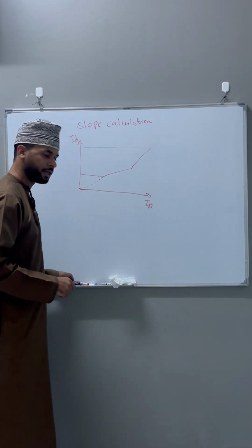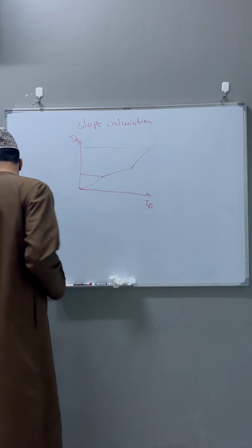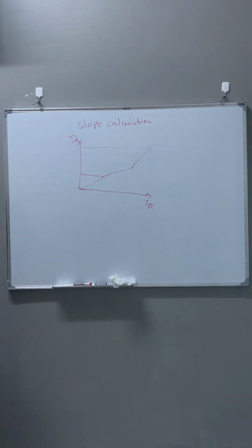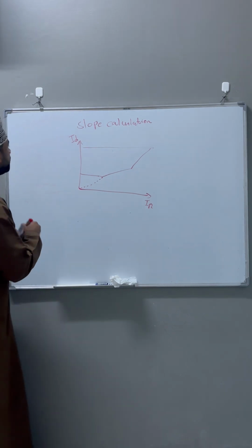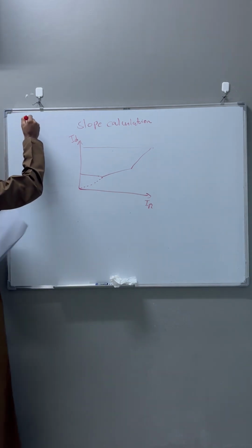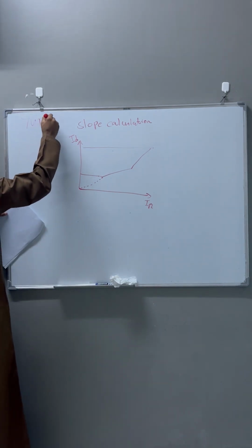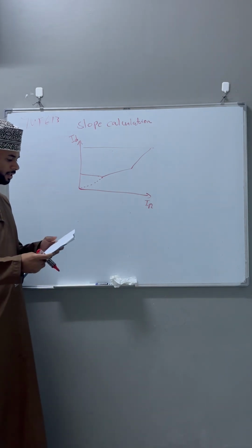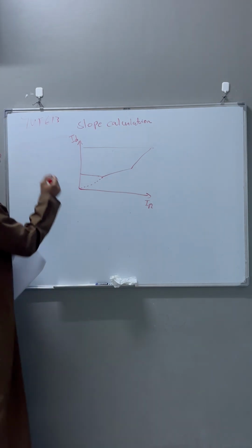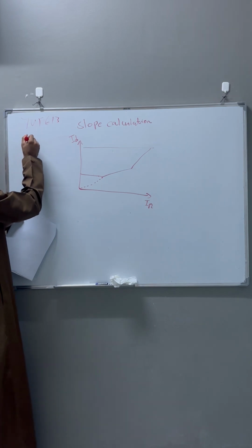I will take a real example. I have here the setting, a real example for the 7UT613. It is a Siemens transformer differential relay. And the client gave me these settings. They gave me the minimum differential current. Okay?